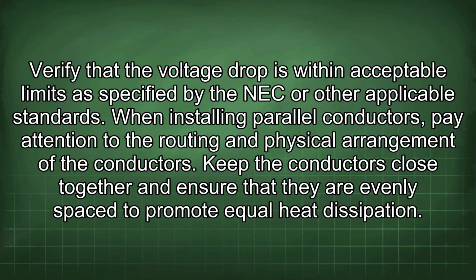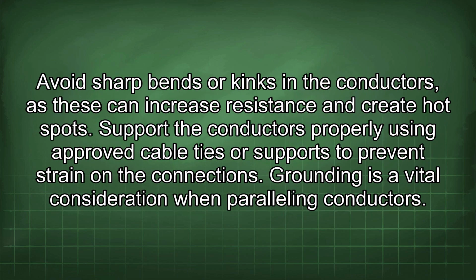When installing parallel conductors, pay attention to the routing and physical arrangement of the conductors. Keep the conductors close together and ensure that they are evenly spaced to promote equal heat dissipation. Avoid sharp bends or kinks in the conductors, as these can increase resistance and create hot spots. Support the conductors properly using approved cable ties or supports to prevent strain on the connections.